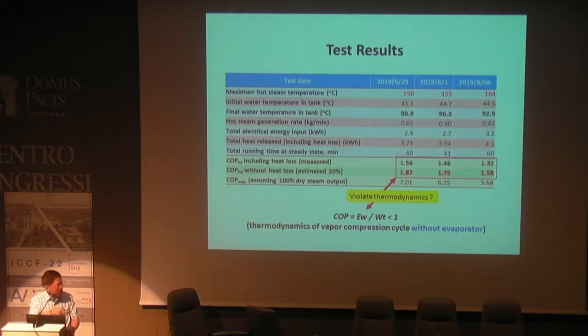The higher steam temperature will lower the COP. It's a measured value. If the heat loss is included, then the COP should be around 0.8, something like that. It's obvious, it violates thermodynamics in all my life. So you cannot believe that, but we did a lot of tests for 2 months, ran the test about 20 times. The same thing happens. And the machine can be run continuously for more than 1 year until the compressor breaks down. Usually a compressor will break down in about 2 years.